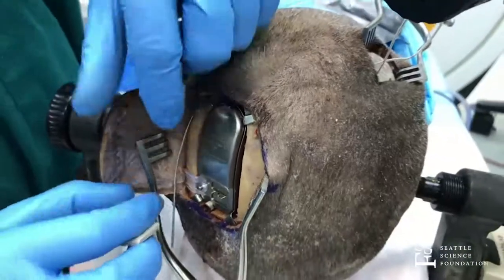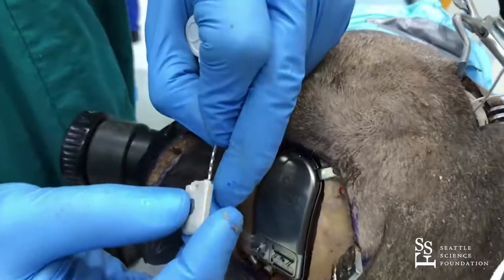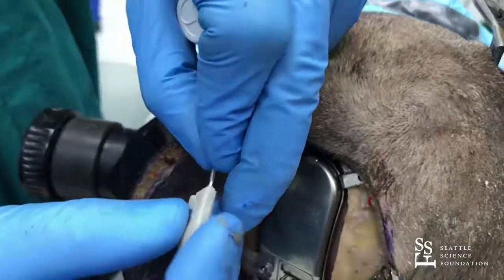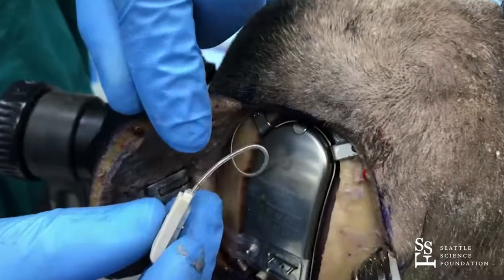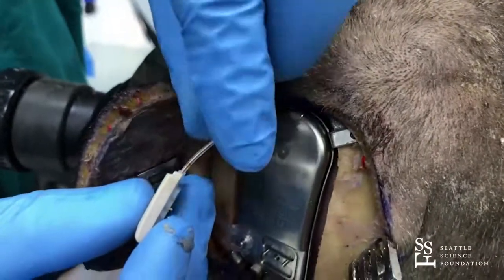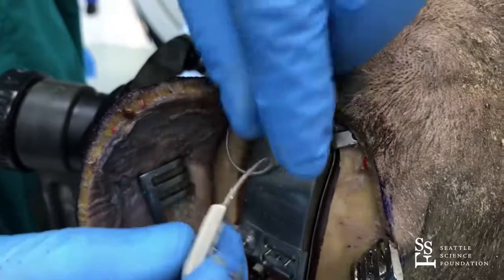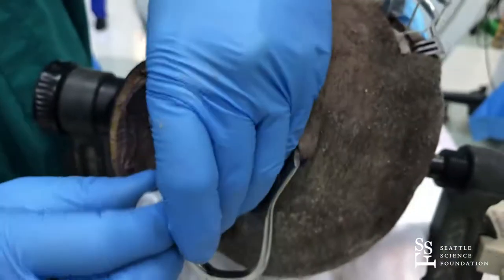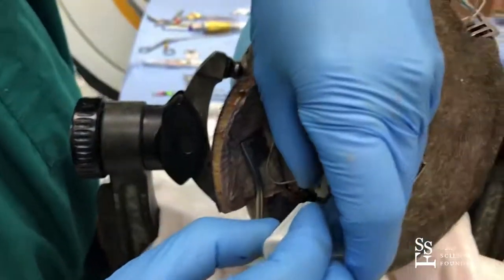And typically we're trying to juggle two electrodes at the same time. We just have one today. And there's actually a little tan line on the electrode, I don't know if you can see it, that you have to have flush with the cover, and then that's how you know it's in all the way. And then we'll lock that down with the torque wrench again.